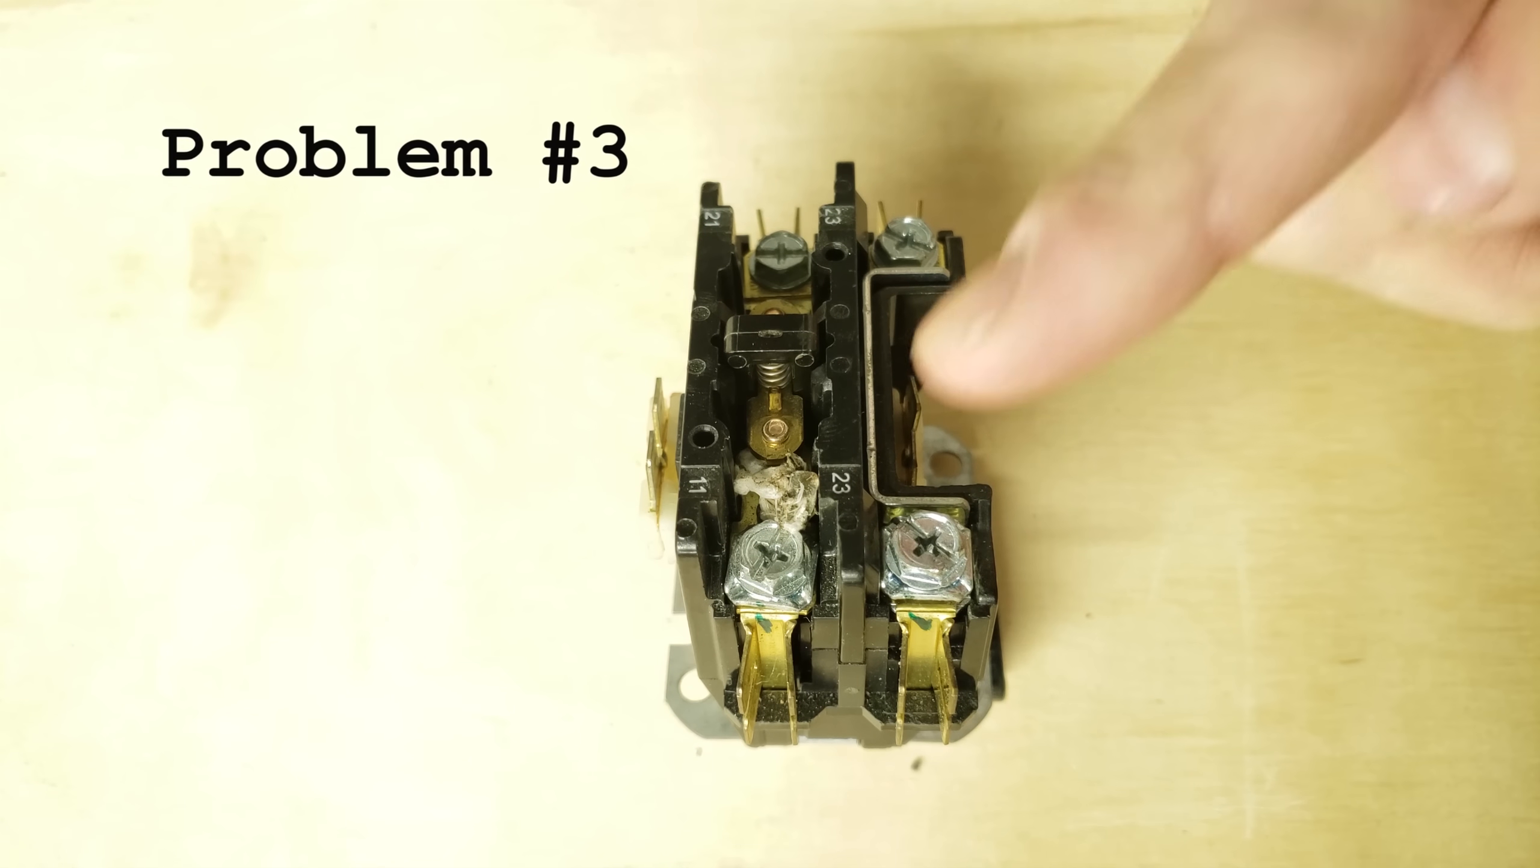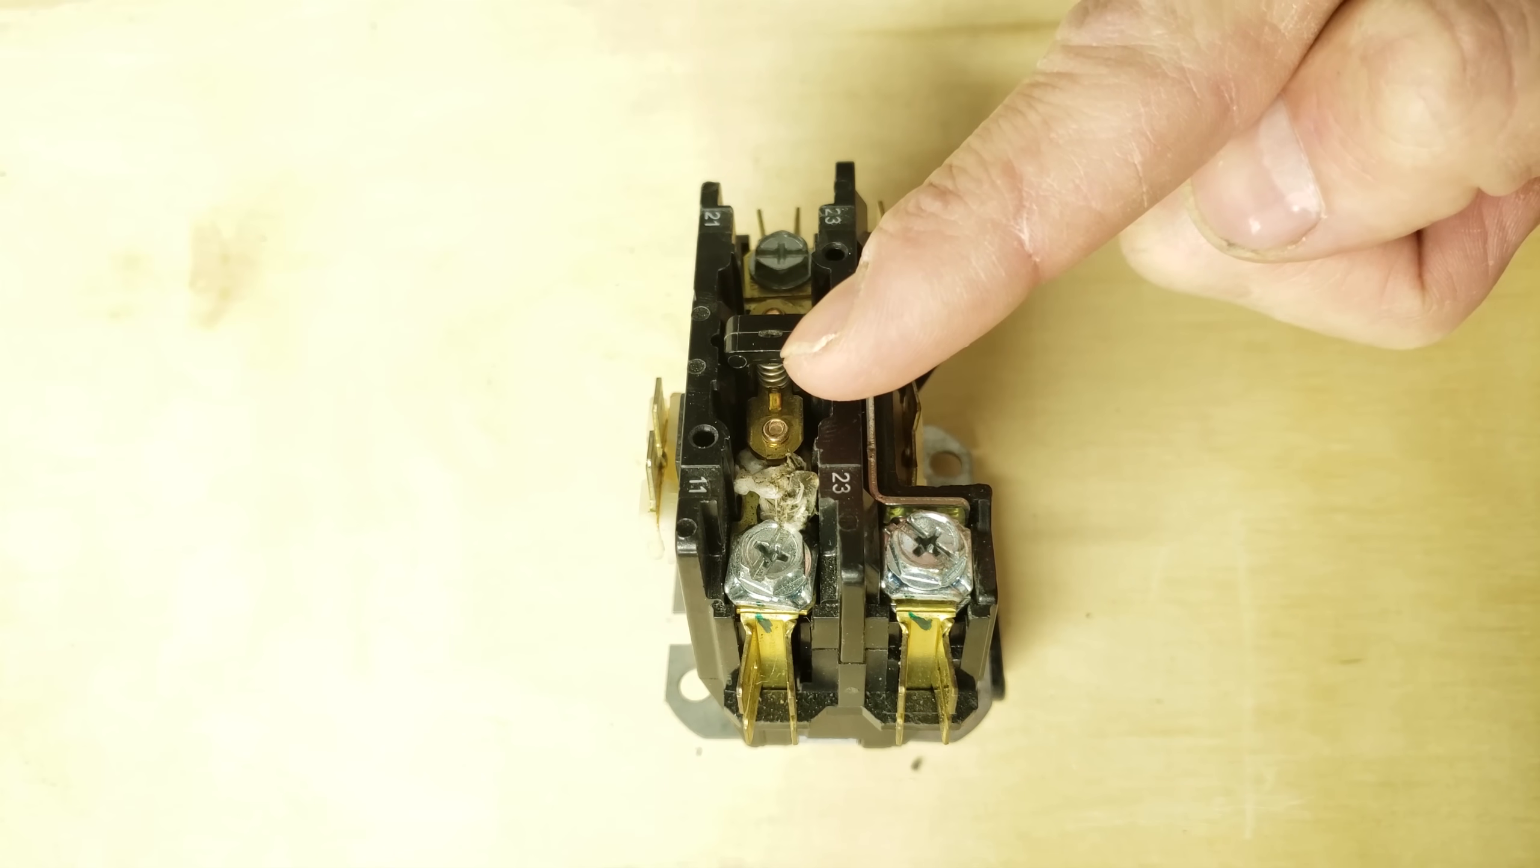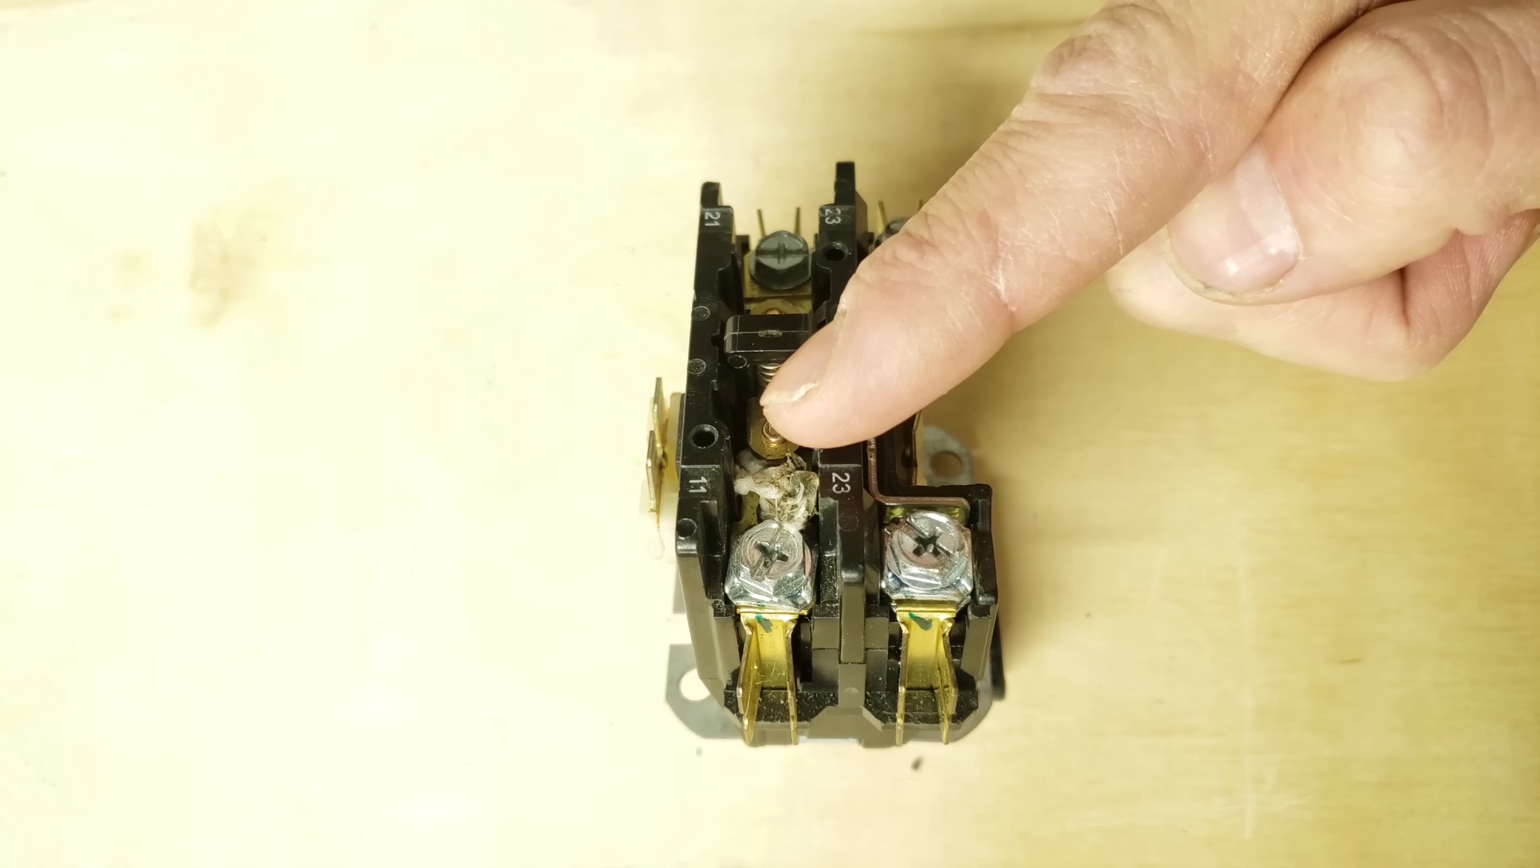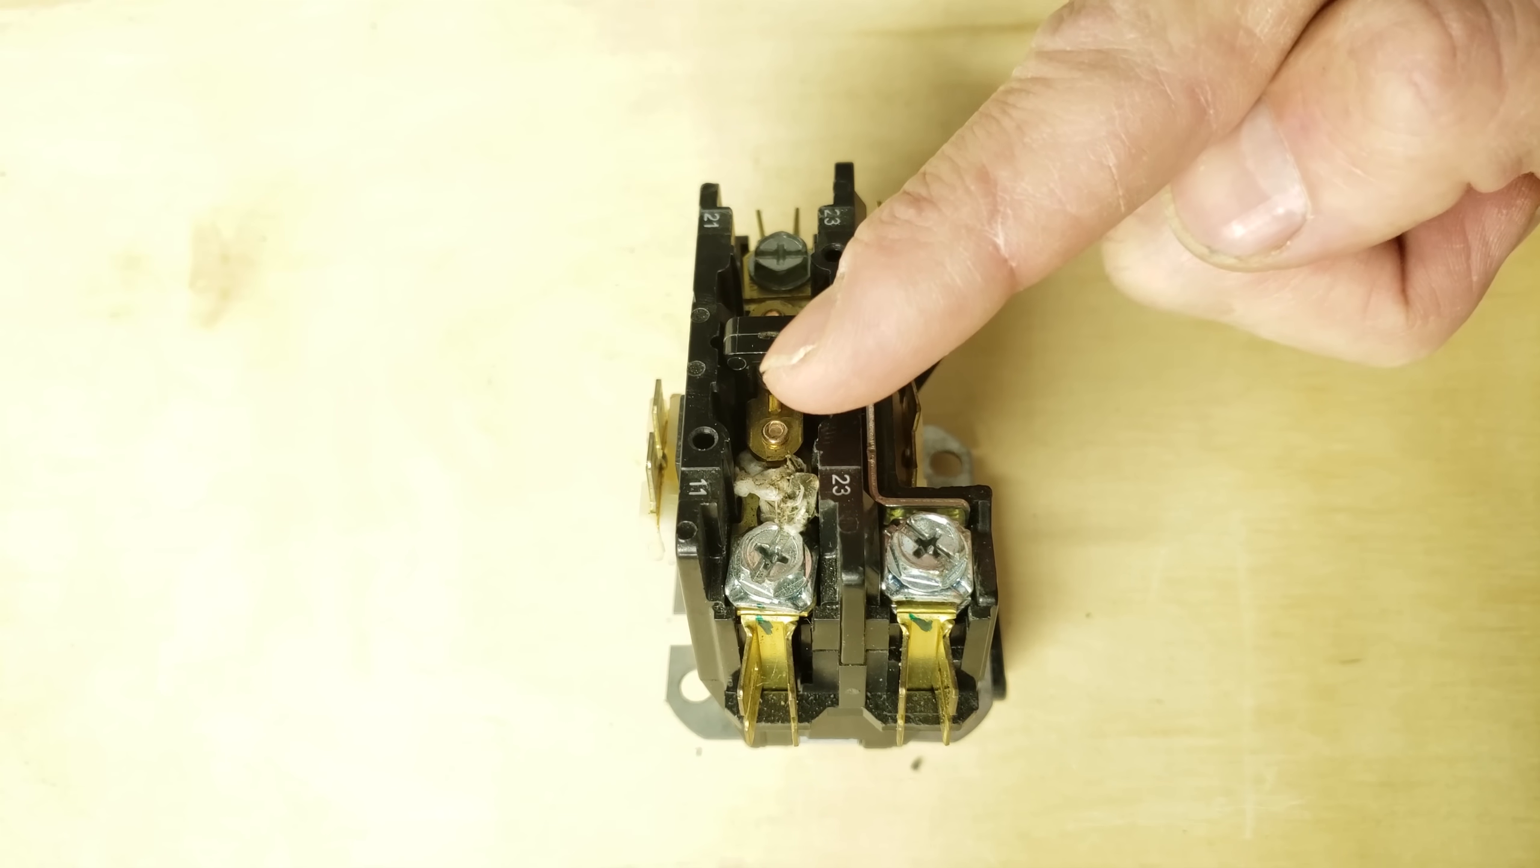Problem number three could be ants or some other type of insect that's inside your contactor, right in the contacts themselves, so when they close they're either hanging up or just not making contact completely. You could also have cobwebs. I find a lot of cobwebs around here and even other trapped insects in the cobwebs. Spiders in there and ants.